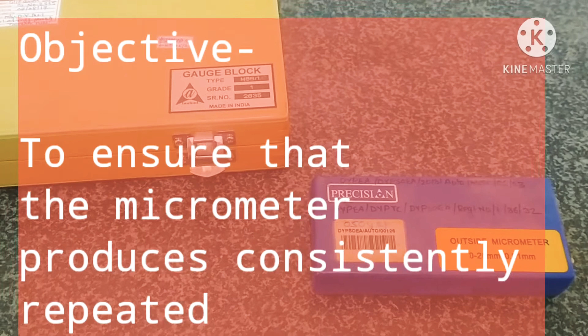Whenever measuring equipment is used, a calibration system should be in place to help ensure that the measurement system does its job. The main thrust of a calibration system consists of a schedule that requires each piece of measuring equipment to be calibrated on a regular basis.